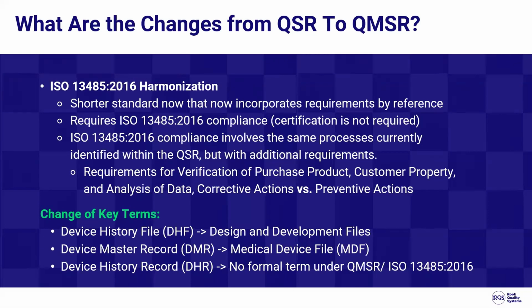Again, this does require 13485 compliance. Although certification is not required, we would definitely recommend it. The compliance, again, involves the same processes currently identified with QSR, but with additional requirements. A couple of examples: 13485, compared to the current 21 CFR 820, has additional requirements for the verification of purchased product, for customer property and analysis of data, and then corrective actions versus preventive actions.